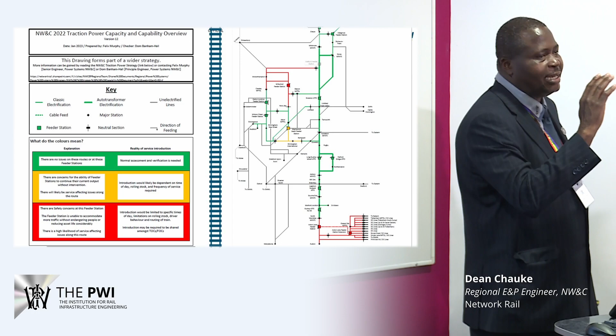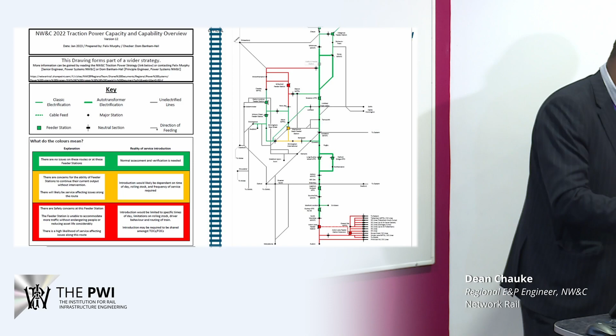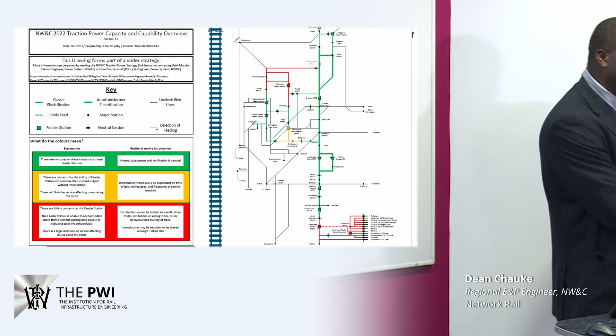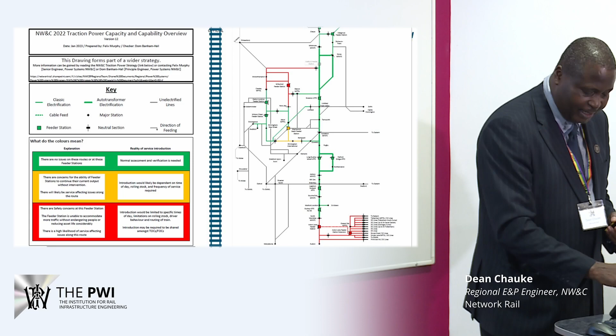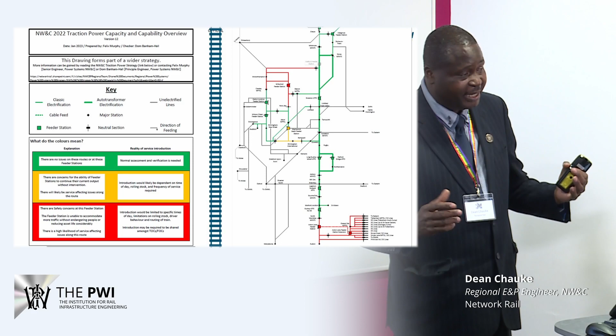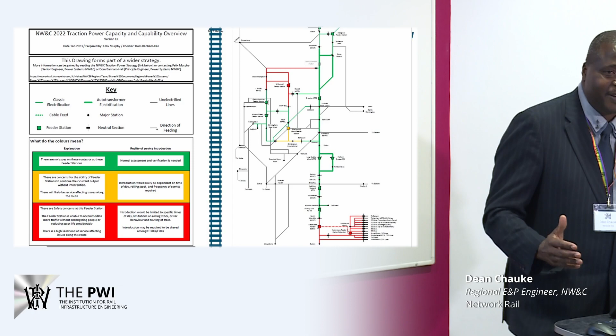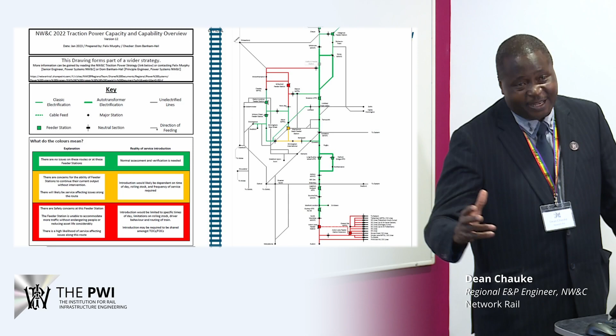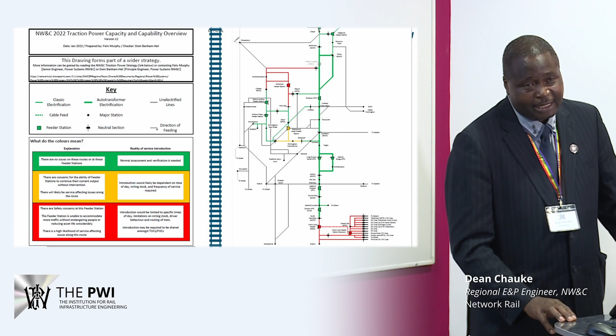If we lose one feeder, we are now overloading the single feeder to about 1.5 times. And if it trips, because it trips to the supply end of the system, it gives us a challenge where National Grid, or in this case UKPN, says there's a problem in your system, let's investigate. Closing the 4-track railways for 10 minutes while they investigate before they energize costs the industry between 500K and 1.5 million for 10 minutes. And once that happens, it stops services from as far as Scotland because there will be congestion further down south, so they are not dispatched on the West Coast Main Line.